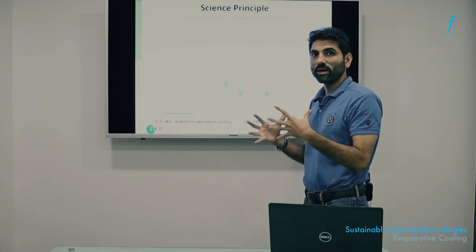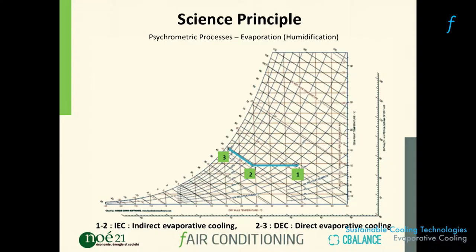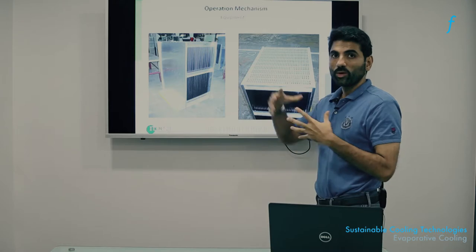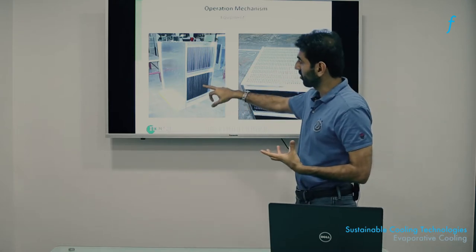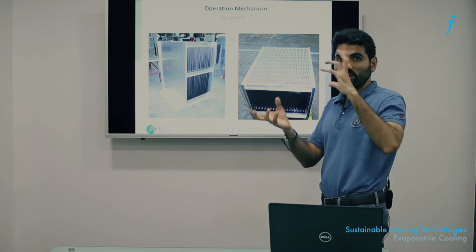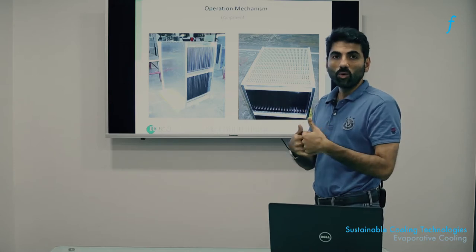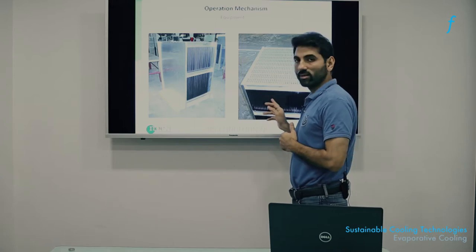The heat exchange unit that performs indirect evaporative cooling looks very different from the cellulose pad used in direct evaporative cooling. In this unit, what makes thermal contact is not water and air directly, but two air streams separated by a thin wall — one stream is the evaporatively cooled secondary air, and the other is the warm primary air from outside. This thermal contact without mass transfer is what makes indirect evaporative cooling unique.